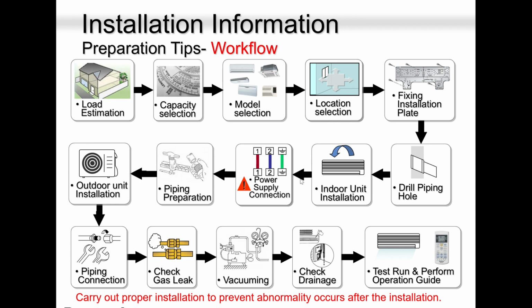Outdoor unit installation is so important. Sometimes on a residential application, they put it next to the kitchen hood. All that oil that is sucked from indoors goes and blocks the condenser fins, the condenser coil. Then it's blocked. Then the system shuts down on high pressure.